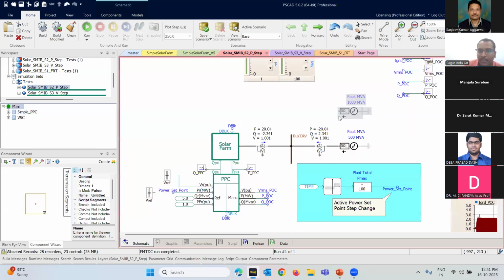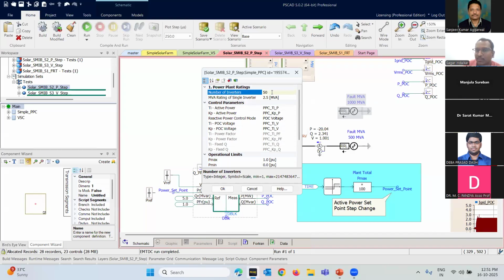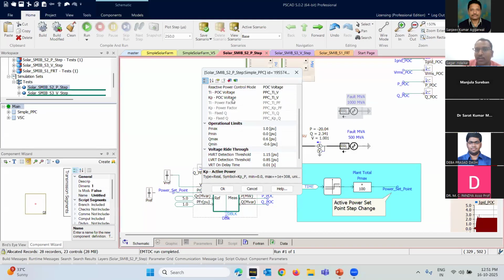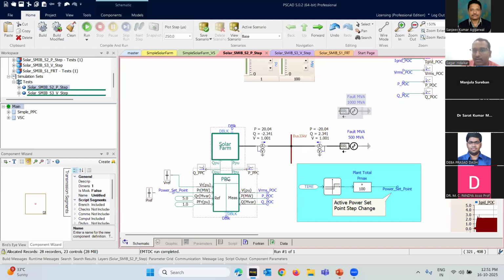So if I right click on this edit parameter interface, I have to specify the plant ratings. I have to specify the values of the PI controller, gains of the PI controller, limits, P limit, Q limit, operating limits of the plant, the LVRT, HVRT threshold below which the PPC should freeze or supply reactive power, or above the threshold above which the PPC should reduce the reactive power support. All these are specified inside the parameter interface.